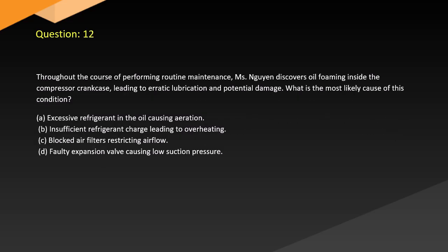Question 12. Throughout the course of performing routine maintenance, Ms. Nguyen discovers oil foaming inside the compressor crankcase, leading to erratic lubrication and potential damage. What is the most likely cause of this condition? A. Excessive refrigerant in the oil causing aeration. B. Insufficient refrigerant charge leading to overheating. C. Blocked air filters restricting airflow. D. Faulty expansion valve causing low suction pressure.